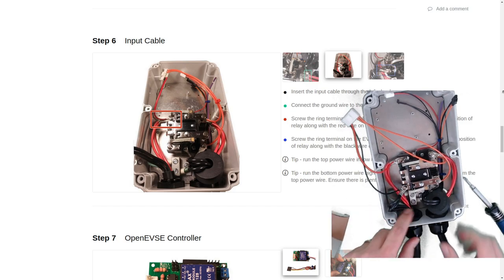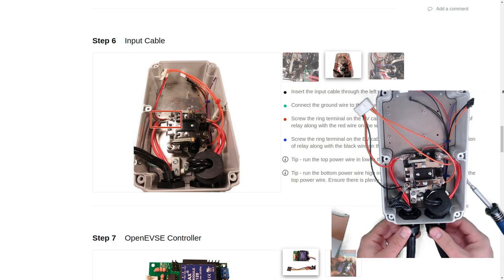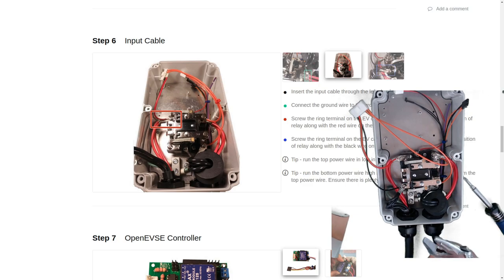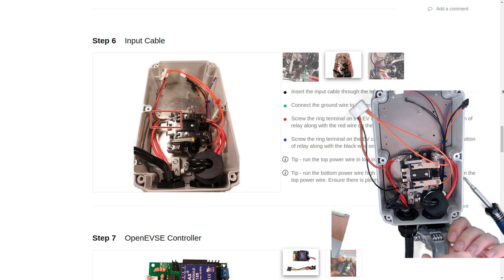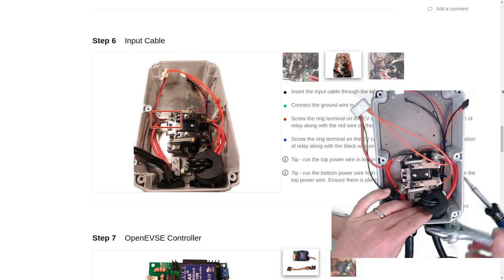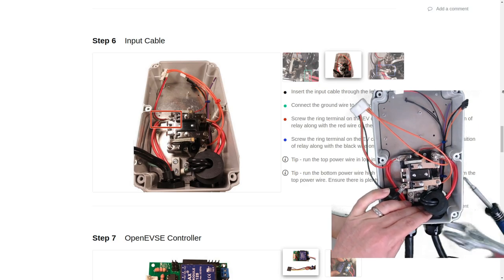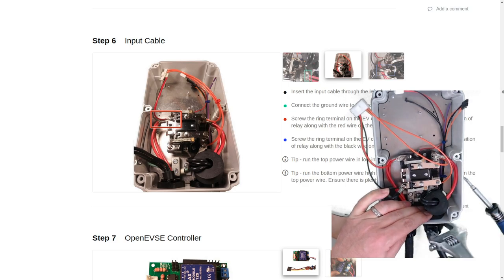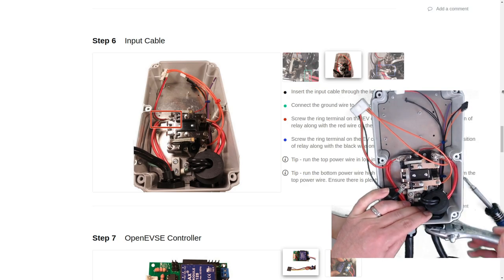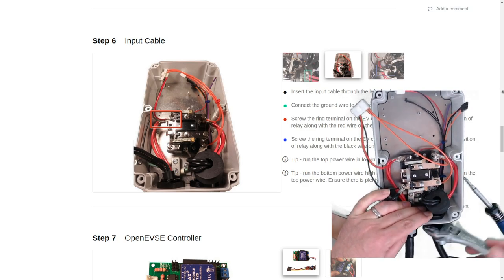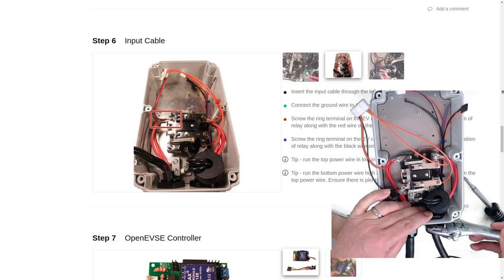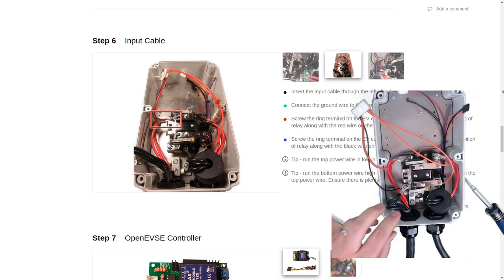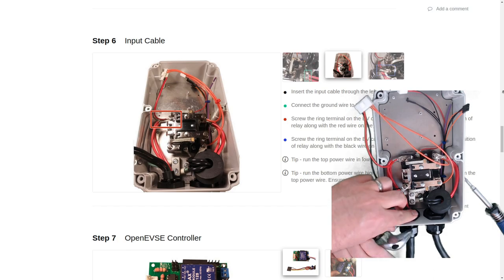So now we'll send those wires kind of up high and make the red ones go down low. Now we can go ahead and tighten the cable glands for both our EV and input cables. To tighten down the glands we'll just use a set of channel locks. And we want to tighten these down to the point where we can no longer pull the cable out. All right, so now it's pretty tight. We'll go ahead and give that a nice pull. And we'll do the same for the input cable.